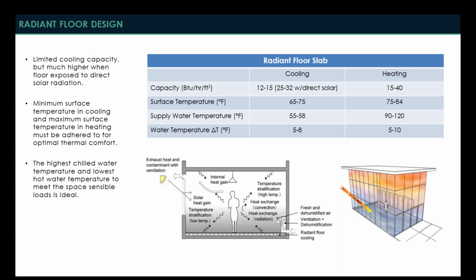And it's important to recognize that the capacity is lower because we'll discuss a little bit further later on how keeping the loads down in your building will allow for the application of some of these radiant systems. The good thing with radiant floor slabs is that when they're in contact with direct solar radiation, whether that's a lobby that has double height glass or an atrium space, the capacity can jump way up by a factor of 2 on the cooling side. And that's really because it's absorbing this energy into the slab before it's getting re-radiated back into the space.